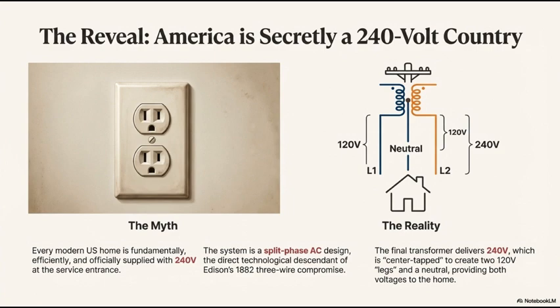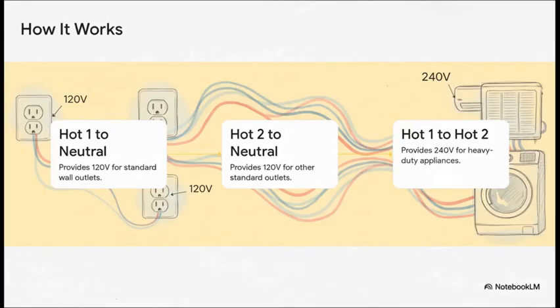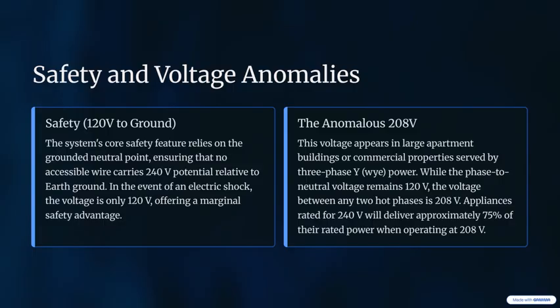But the critical safety math there, the compromise at the core of my position, is the grounded center tap. This is an engineering inheritance from Edison's original three-wire system. By grounding that center connection, the system ensures that the potential between any accessible hot wire, L1 or L2, and earth ground is only 120 volts. This gives us a marginal but mathematically crucial safety buffer. If we look at Ohm's law, V equals I times R, where R is, say, human body resistance, halving the driving voltage from 240 to 120 necessarily halves the resulting current, the I, that flows through a person during a shock.